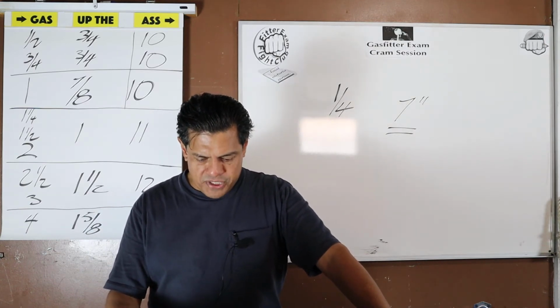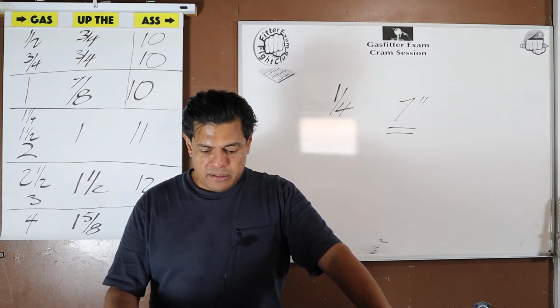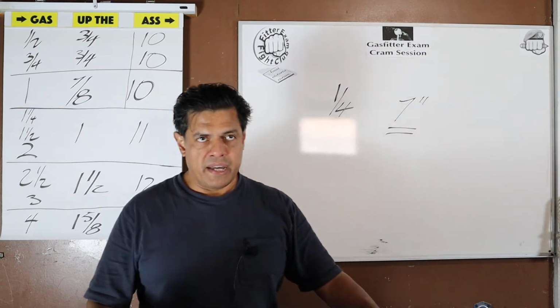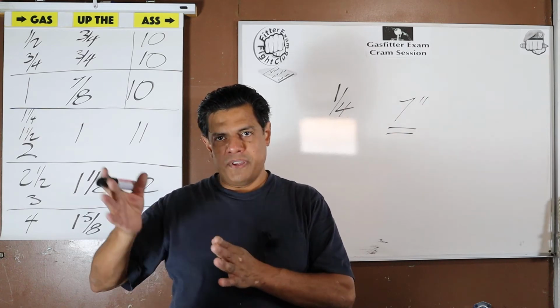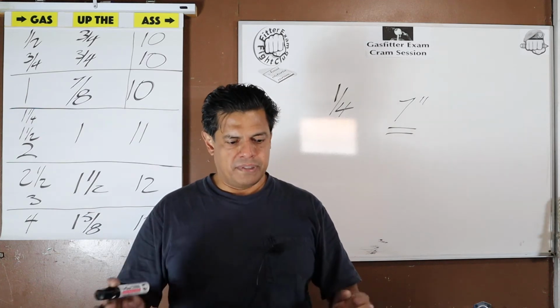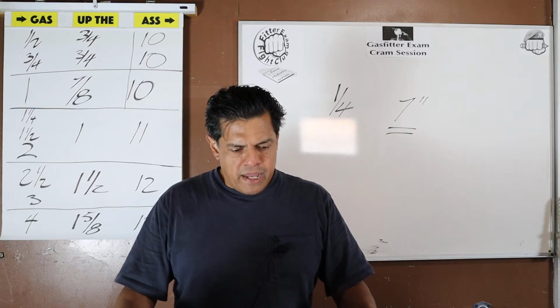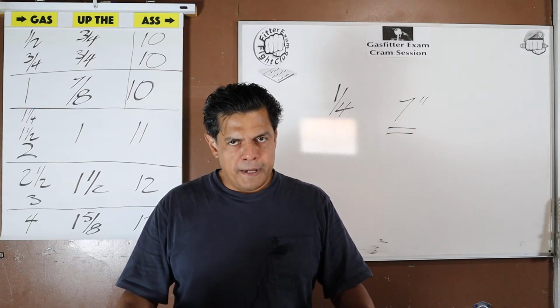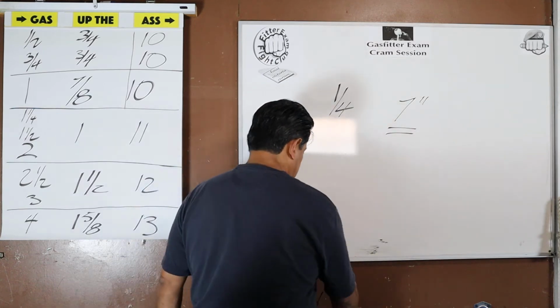Question 4. The shutoff valve shall be in the same room as the appliance. We went over why that's such a good idea. And again, it's going to be within 6 feet. And the appliance valve shall be upstream of the union, because the union is downstream of the shutoff valve. Okay. Page 24. Question 5. A union shall be located within 6 feet of the appliance. 6. That's our magic number, okay?